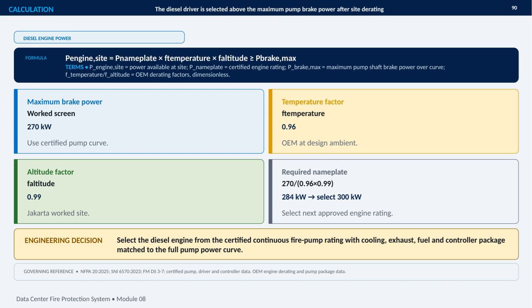In this worked example, the maximum brake power is 270 kilowatts. The temperature factor is 0.96, based on the OEM design ambient, and the altitude factor is 0.99 for the worked Jakarta site. So, the required nameplate rating is calculated as 270 divided by 0.96 times 0.99, which gives approximately 284 kilowatts. Because the engine must use the next approved rating, the selection becomes 300 kilowatts. That rating also needs to be provided as a complete, matched package, including cooling, exhaust, fuel, and controller components. The final decision is therefore based on certified pump, driver, and controller data, together with the applicable NFPA, SNI, and FM references.